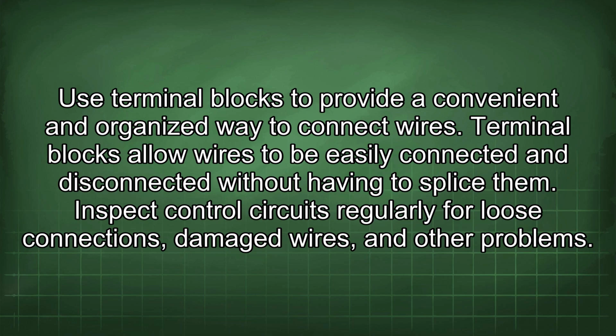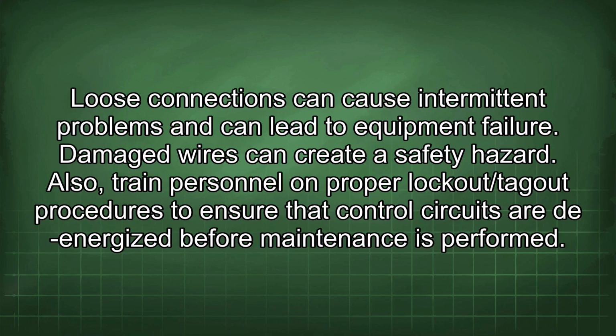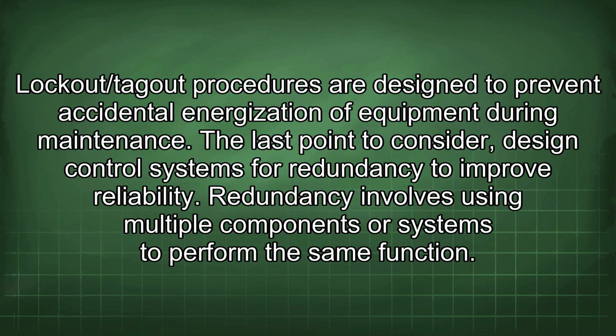Inspect control circuits regularly for loose connections, damaged wires, and other problems. Loose connections can cause intermittent problems and can lead to equipment failure. Damaged wires can create a safety hazard. Also, train personnel on proper lockout/tagout procedures to ensure that control circuits are de-energized before maintenance is performed. Lockout/tagout procedures are designed to prevent accidental energization of equipment during maintenance.